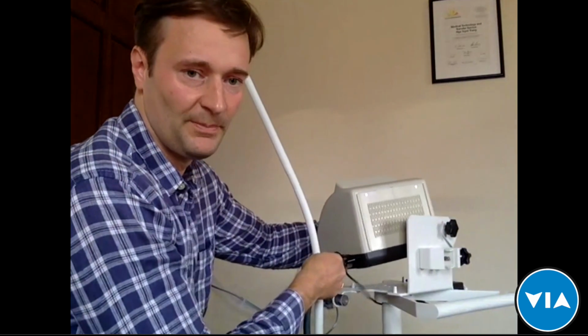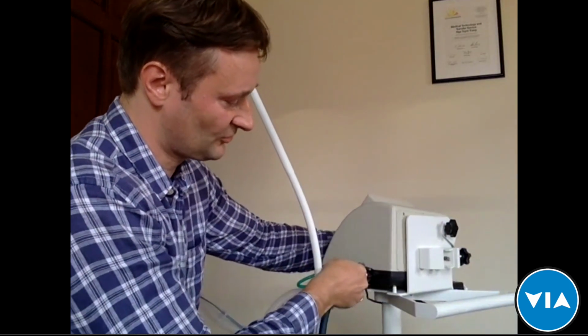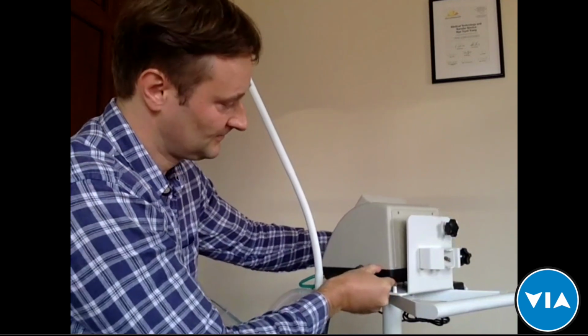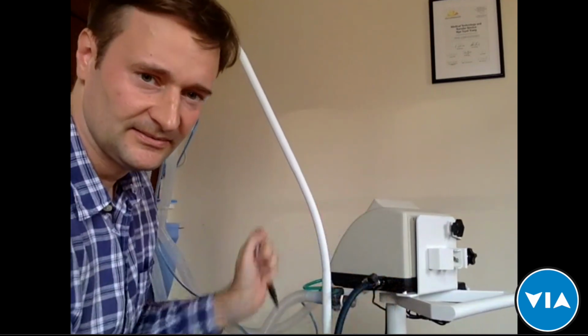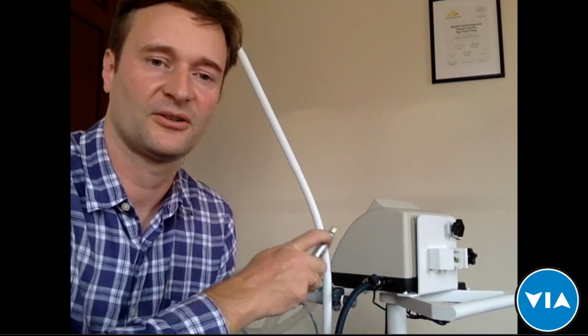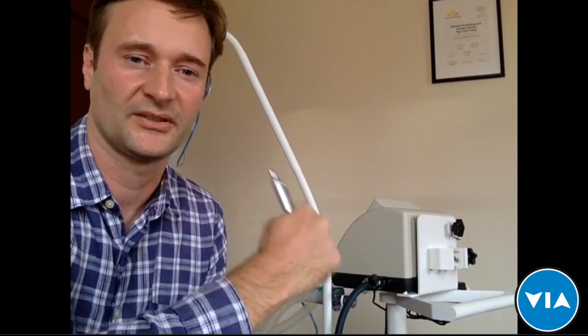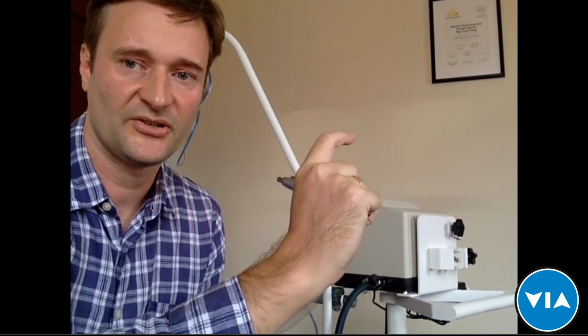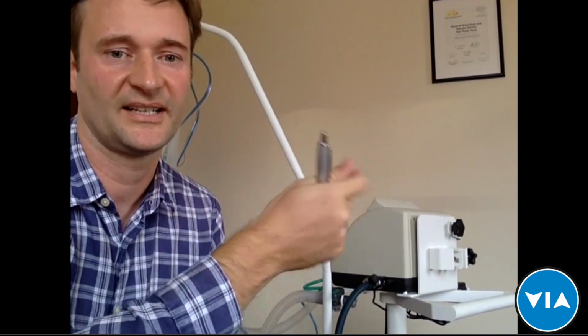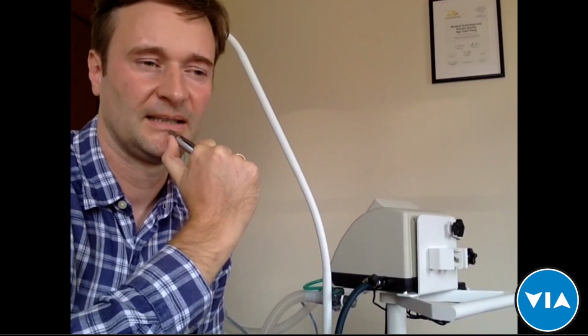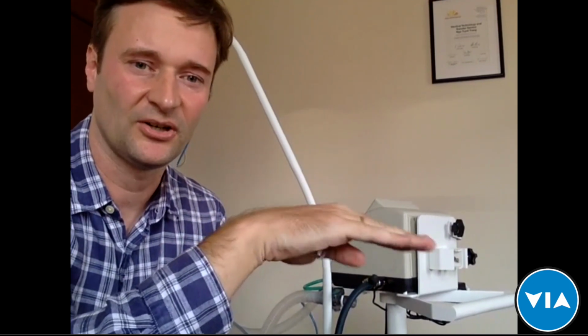And behind there's a control panel where you have access to the oxygen sensor and the filter. The filter should be changed every 6 months, because the device has its own air compressor. It doesn't take air externally, you only need to provide the oxygen. So the air filter should be changed, and the oxygen sensor is rated for about 2 years, depending on the oxygen use. So this oxygen sensor has to be changed every 2 years.